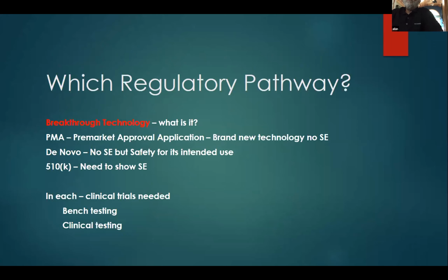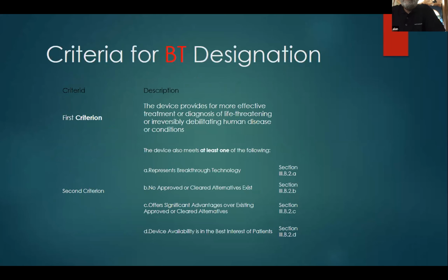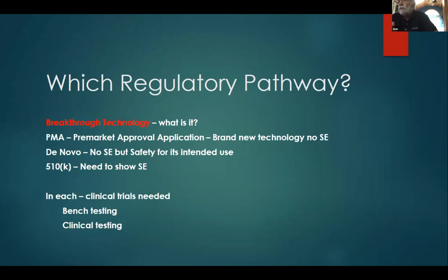So if you want to state that yours is a breakthrough technology, you should be using these criteria that the FDA has outlined for determining if it's breakthrough technology. Now, like I said, with breakthrough technology, supposedly the FDA will work with you in moving this up in their review process. You still have to do all the testing. You still have to have all the proof of the efficacy and the safety of the device. But you could use the terminology.